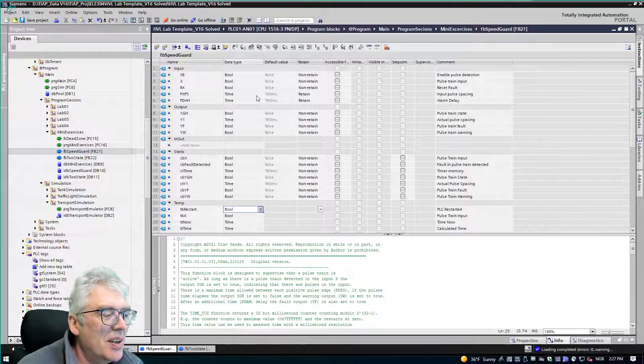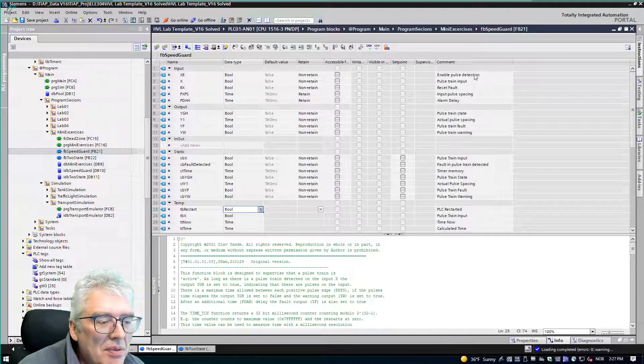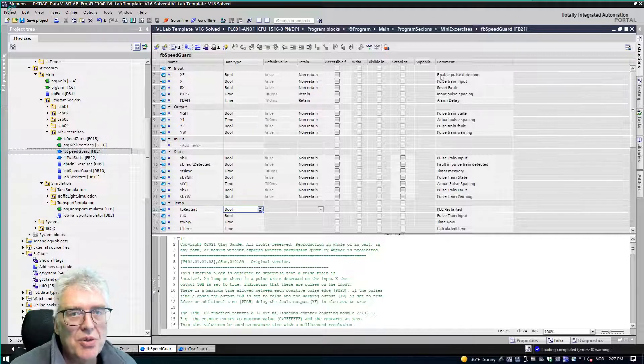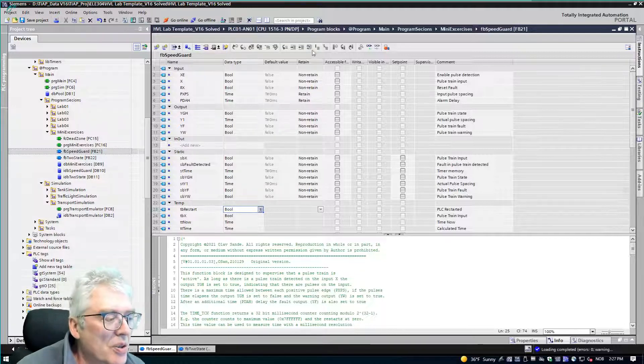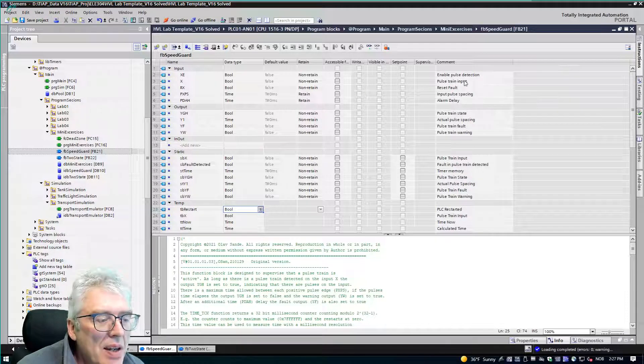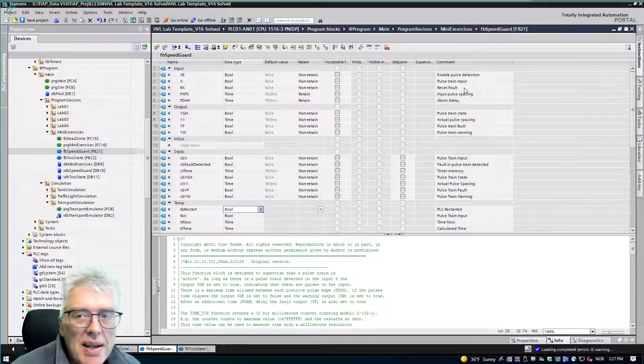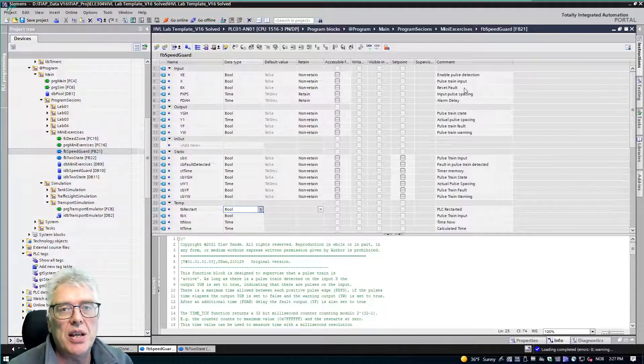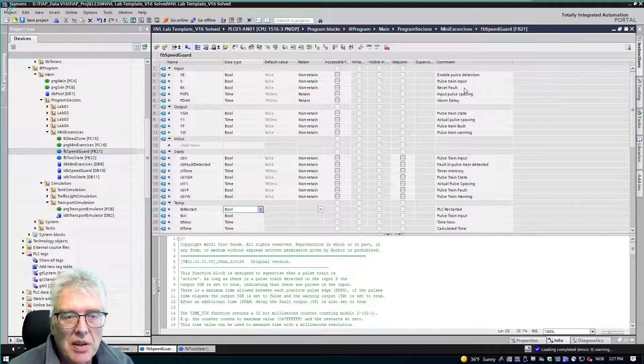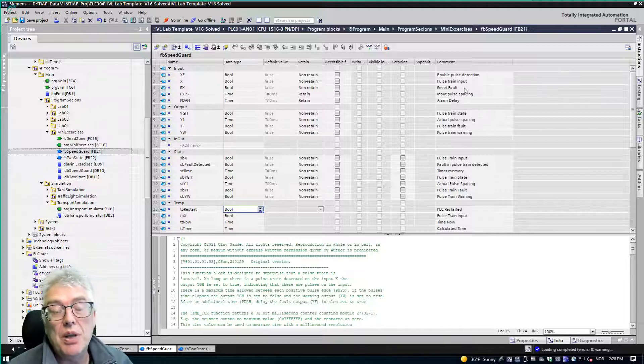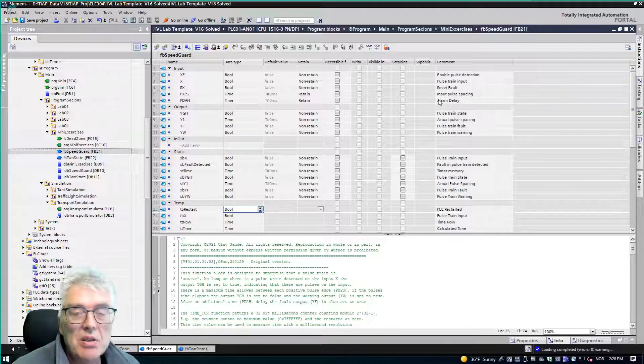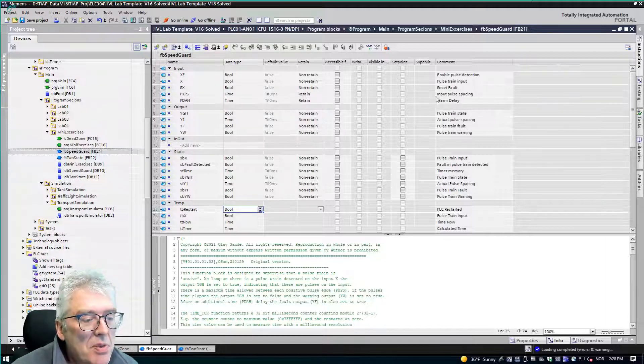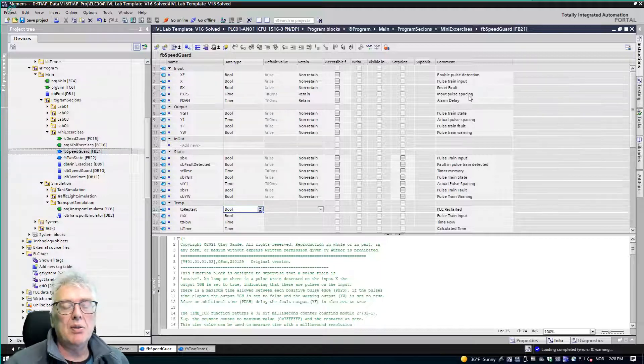Here is the function block. Looking at the inputs first: there's an enable for pulse detection — if it's not enabled, it won't report anything as moving. There is the pulse train input and a reset: if you get a fault, this function block has to be reset. It just stores the fault until reset, so even if pulses start again it must be reset, because this is for safety — someone has to inspect it and reset the function block.